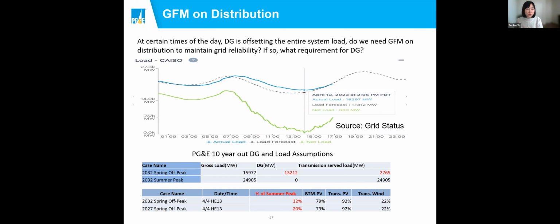I don't have a lot of time to do more research, but I think it could be another topic that we need to think about in the future before it comes. And the last two tables are basically some scenarios in the future that we're seeing. And we're obviously seeing potentially a lot more likelihood that you're going to see either zero or negative gross load on the system, meaning that DG could be taking over from time to time during the day the grid load serving and reliability responsibilities. And we probably need to think about in that scenario what are the additional reliability requirements we need to put on DG and how grid forming inverter would help in that scenario.